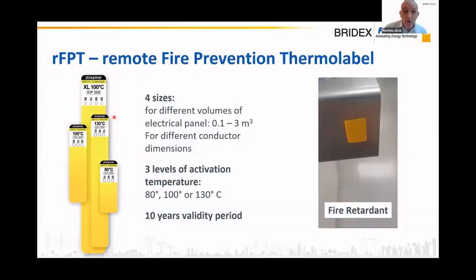There are two reasons why we have different sizes. One, as you might understand, is the size of the conductor. The second one is the size of the panels. The stickers and the sensor need to be located inside the same compartment, but the sticker needs to hold a certain amount of gas that can fill the panel enough so that it's detected by the electronic sensor. And we have different levels of activation that can be chosen at the moment you place the order, and it can be 80 degrees, 130 degrees, or 100 degrees, as you can see here.